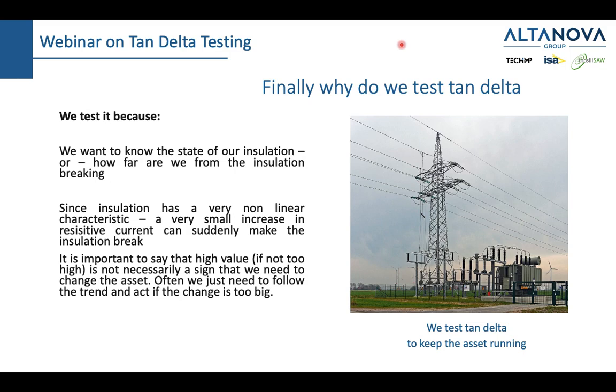And finally, to answer the question, why do we test Tan delta? We test Tan delta because we want to know the state of our insulation, or we want to know how far we are from the insulation breaking. And since insulation has a very nonlinear characteristic, a very small increase in resistive current can suddenly make the insulation break.